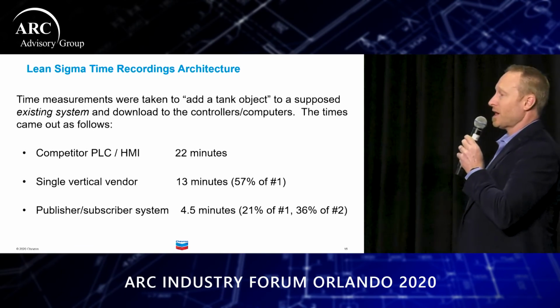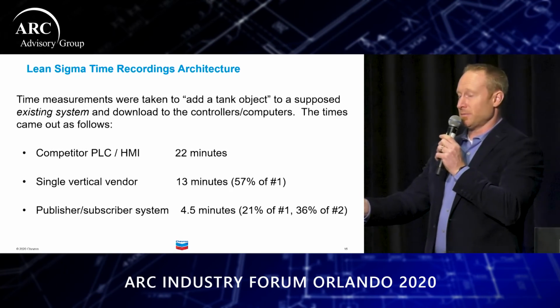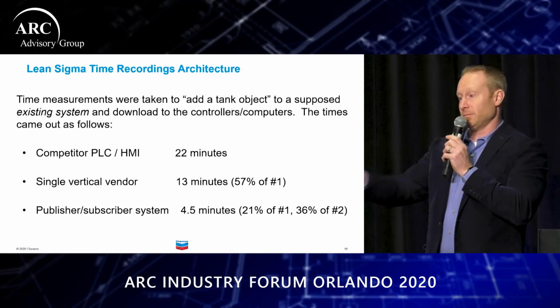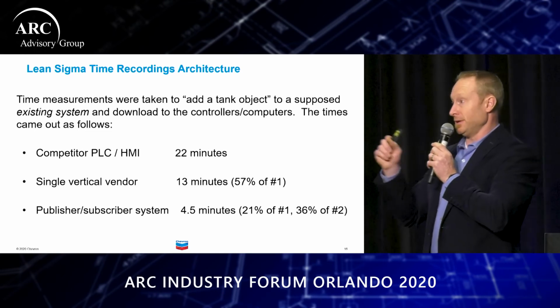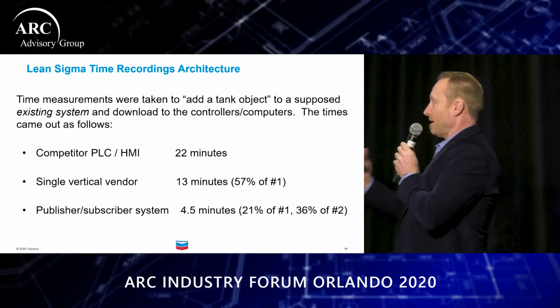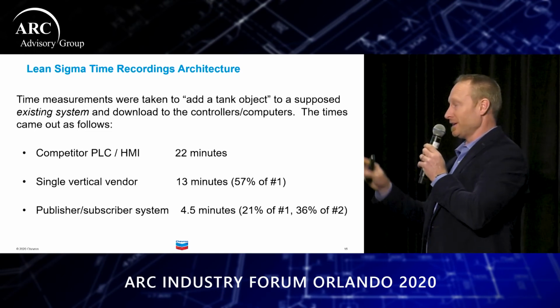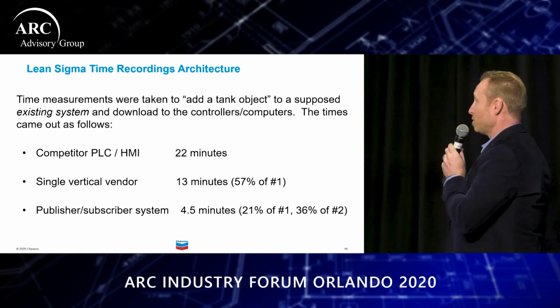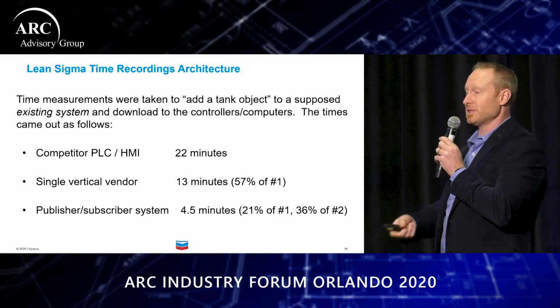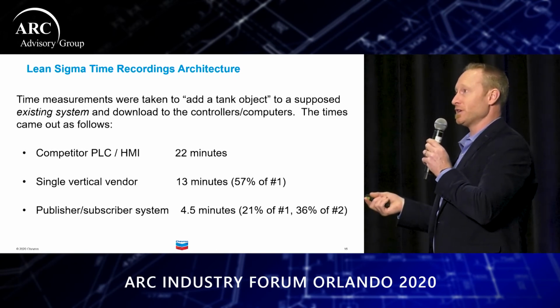And then publisher-subscriber was: add the tank object, link the 4 to 20 milliamp signal into it, and hit save—going online with the PLC, going offline, all that stuff taken into account. That came out to 20% of what it took to do the integration before.